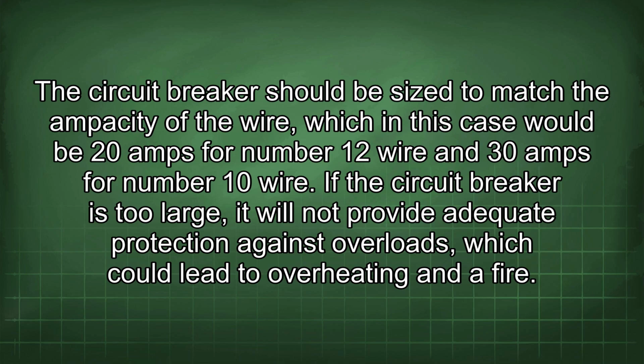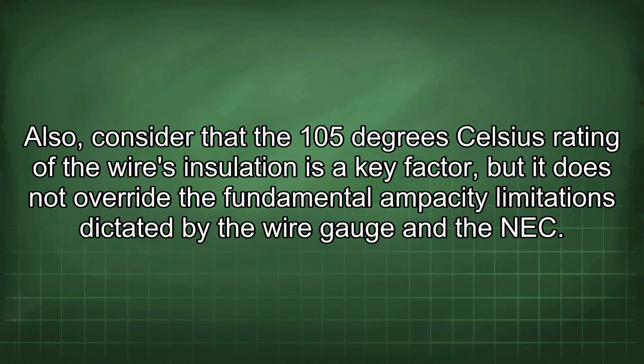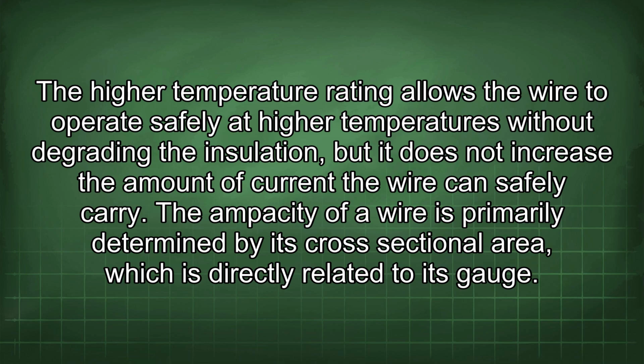If the circuit breaker is too large, it will not provide adequate protection against overloads, which could lead to overheating and a fire. Also, consider that the 105 degrees Celsius rating of the wire's insulation is a key factor, but it does not override the fundamental ampacity limitations dictated by the wire gauge and the NEC. The high temperature rating allows the wire to operate safely at high temperatures without degrading the insulation, but it does not increase the amount of current the wire can safely carry.